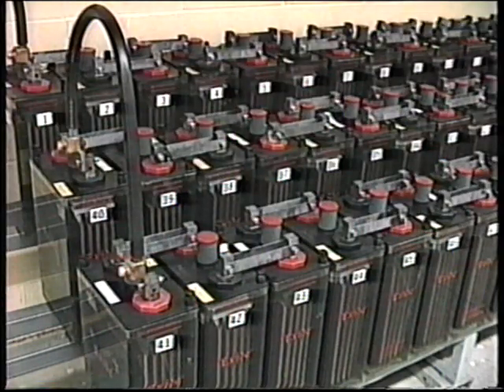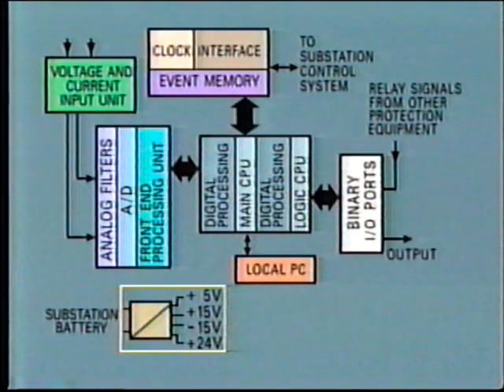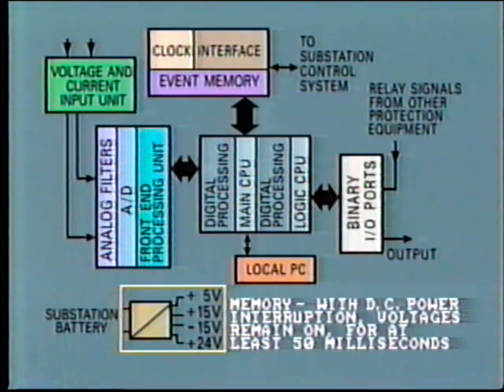As with other relay units, the power supply is provided from the station battery. In the relay power module, this is broken down to the various voltage levels required by the computer, say plus 5 volts, plus 15 volts, negative 15 volts, plus 24 volts. A memory is included so that even in the case of DC input power interruption, these voltages will remain on for at least 50 milliseconds.